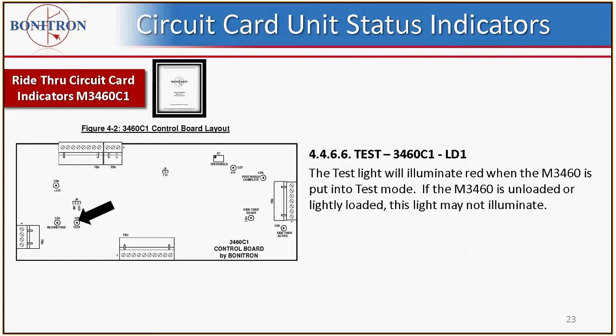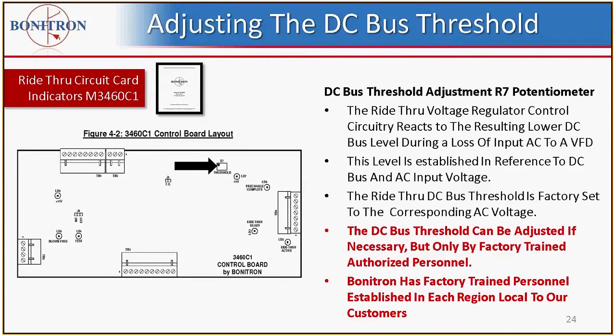The test light will illuminate red when the 3460 is put into test mode. Once again, depending on the DC bus level, there may not be enough for it to boost high enough to be able to indicate.